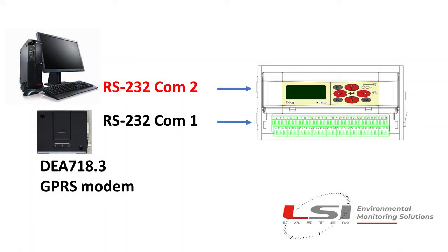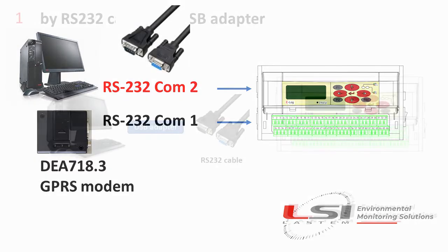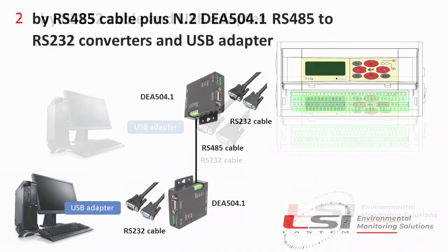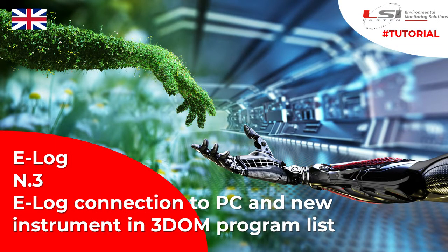Data stored inside E-Log internal memory can be downloaded using GPRS modem or direct cable. As direct cable we have three options: by RS-232 cable with USB adapter, by RS-485 using DEA 504.1 RS-485 to RS-232 converter, by Ethernet using DEA 553 RS-232 to Ethernet converter. Watch tutorial number three to learn how to detect the PC port number assigned to the USB adapter.